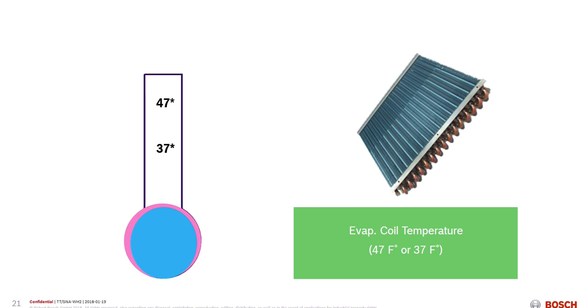Well, how do I communicate? My unit comes out of the box with the logic of looking at your sensor, looking at that indoor unit, with the 47 degree saturation temperature in mind. So what I'm going to do is look at that target temperature and modulate up and down so that my refrigerant saturation temperature is going to be 47.